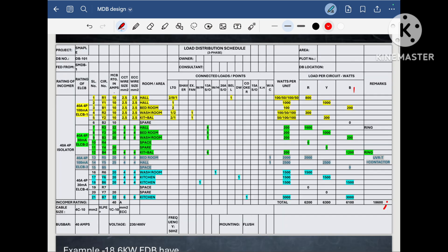Now let us analyze one DB schedule in order to get the demand factor. Here there is a flat DB — final distribution board load schedule. This flat has different types of load: light load, shaver socket, exhaust fan, washing machine, single socket, water heater, 20 ampere socket, bell, dishwasher, cooker, 15 ampere socket, and window AC. When we tabulate this load schedule, we find that this flat has a total connected load of 18,600 Watt, that is 18.6 Kilo Watt.